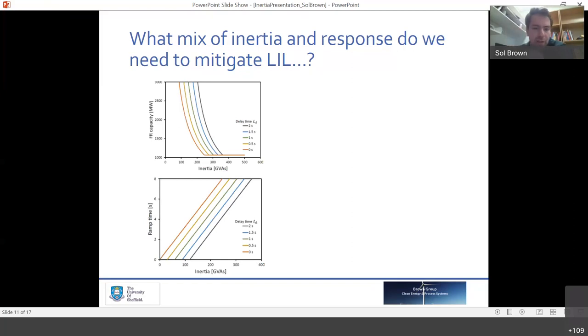So if we ask ourselves what mix of inertia and frequency response we need to mitigate the largest infeed loss in the UK, then we can apply our analysis and produce these plots. On the top graph we have the frequency response capacity, and on the bottom on the x-axis we have the inertia, and you can see that there's this exponential type behavior, and then we have a point at which we hit a level of inertia where things blow up. These are plotted against the delay time of the frequency response. So the slower the frequency response, the greater amount of inertia that you need on the system. So that's intuitively correct.